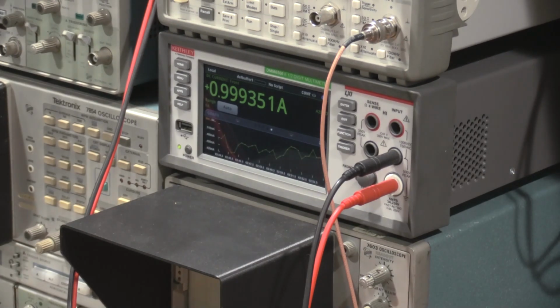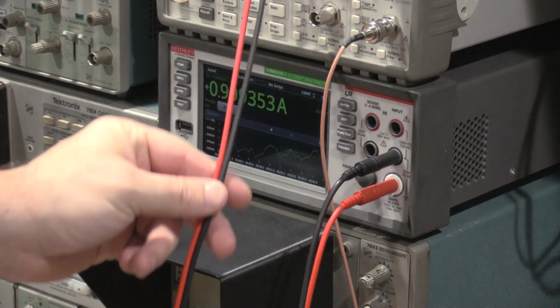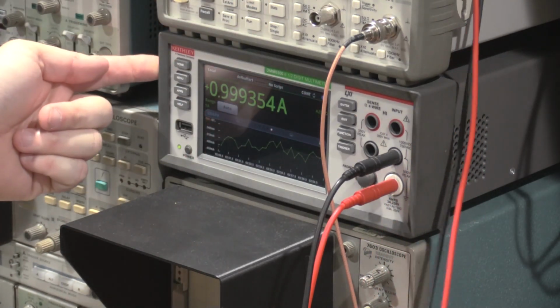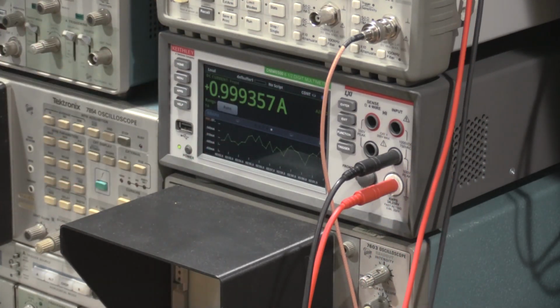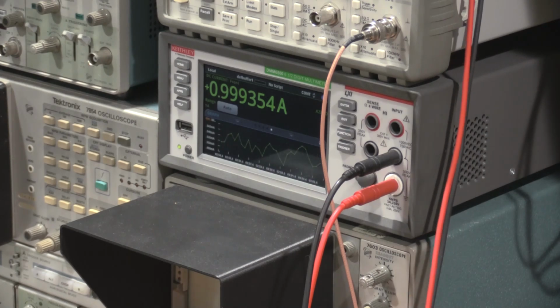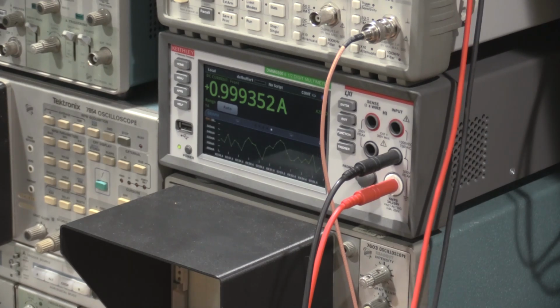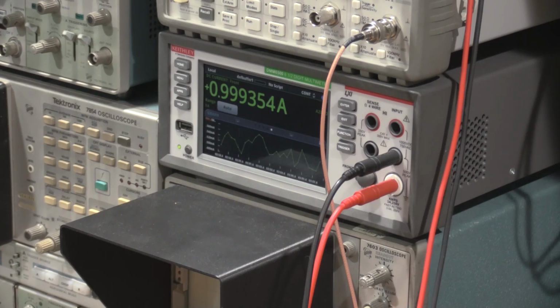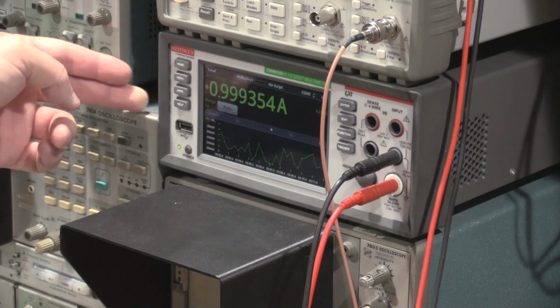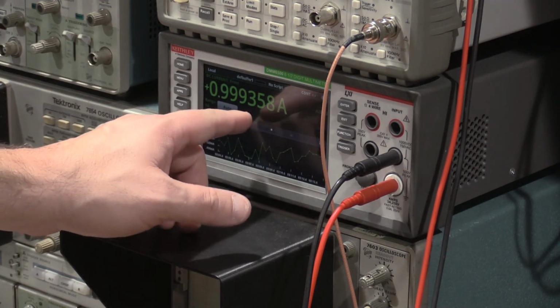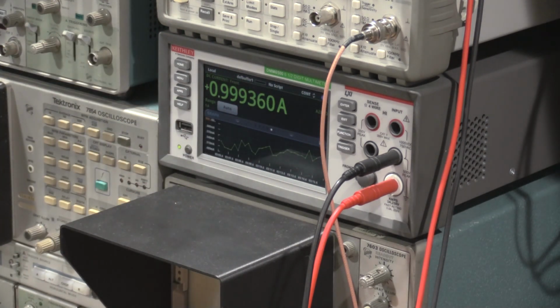This is also my 6500, so this is not the highest precision meter we have in the lab. Most of the calibrations I've done are referenced to the 7510, which is a 7.5 digit meter. And the 7510 has a much, much better internal reference than the 6500 does, so its stability is a lot higher. So this stuff bouncing around at the end doesn't concern me at all.